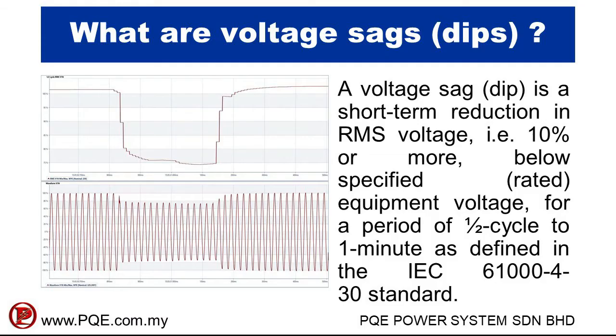What are voltage dips? A voltage dip is a short-term reduction in RMS voltage — i.e., 10% or more — below the specified rated equipment voltage, for a period of half a cycle to one minute.